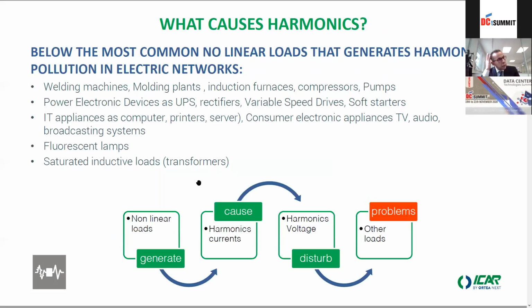So the most important causes of the harmonics are especially the loads that are very, very varying. Loads like welding machines, molding machines, electronic devices, UPSs, computers in general, loads like fluorescent lamps, etc., can create a lot of harmonics that will be distributed in the line.